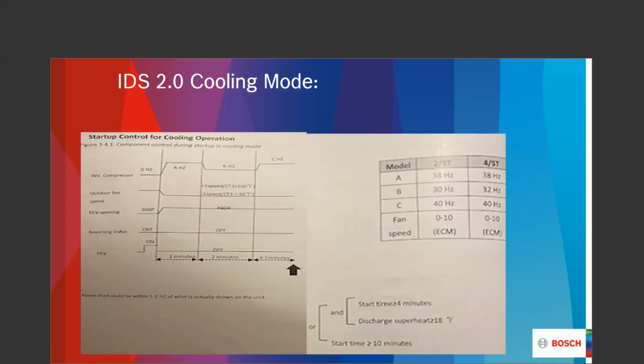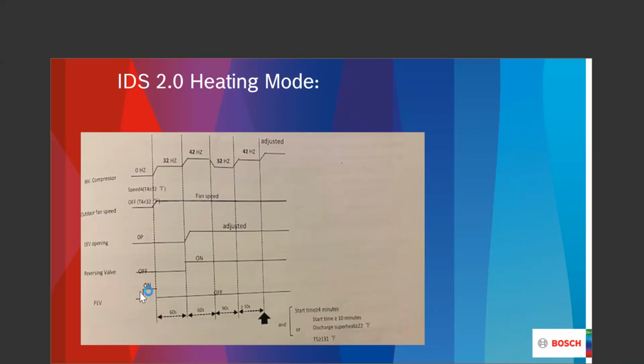Okay. Now, the 1.0 staging is similar to this. It's a little bit elongated. So that 1 minute may be 2.5, and that 2 minutes may be 2.5. It's just a little bit elongated from the 2.0. The 2.0, it seems to us, is almost half of the time frame of the allotment time of staging from the time that we get that Y call to the time that we are literally in the 38 hertz to 42 hertz range, so that we can start the process of what the thermostat wants us to do. So when we go to the heating mode, again, a little bit different.